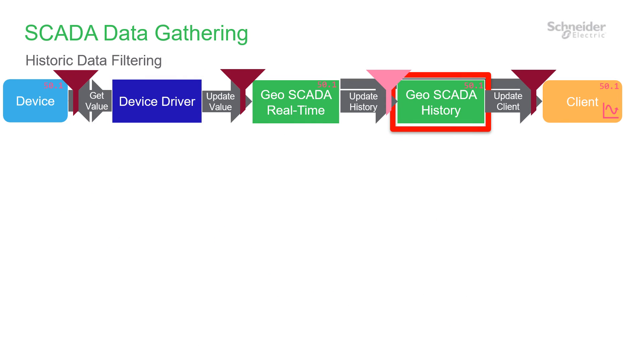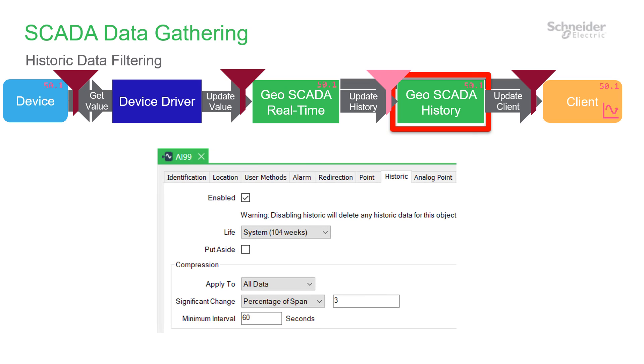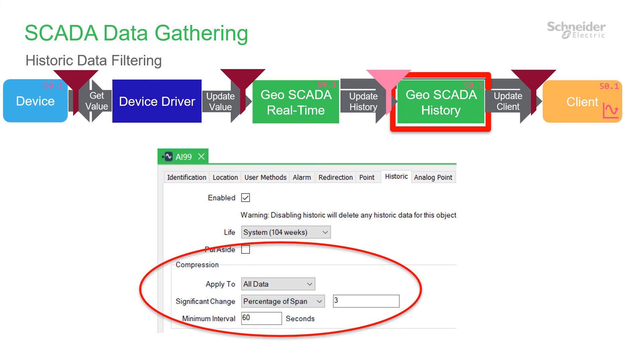Let's move to the next step: the historian. A well-configured system will store only the historic data which is needed for trends and data analytics. The GeoScada historian allows a filter to be set up for every point. This can choose to write history using change size and/or time interval. Here you can see the choice is to filter out changes smaller than 3% and prevent storage of consecutive values within one minute. You can pick values suitable for your application.